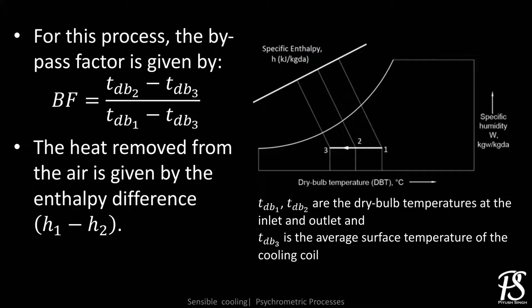This can be explained with the help of bypass factor. It gives us a measure of the extent to which air reaches the mean effective surface temperature of the coil. Mathematically, it can be calculated by an expression which is the same as the ratio between the temperature drop that could not be achieved to the maximum possible temperature drop.